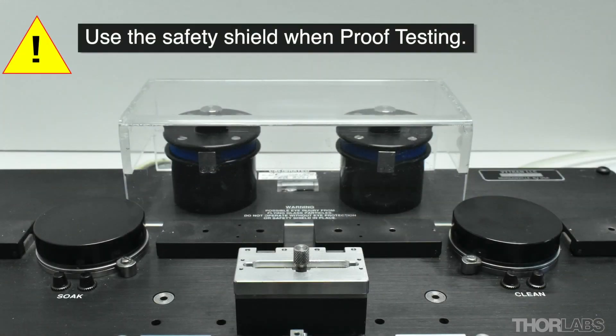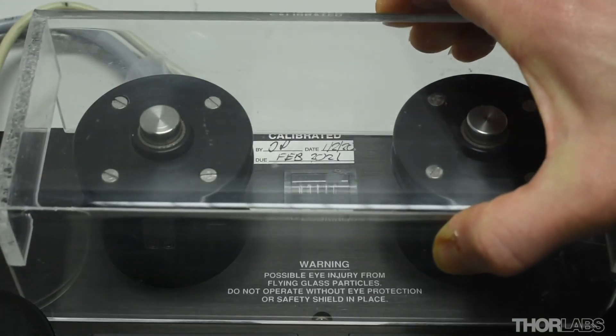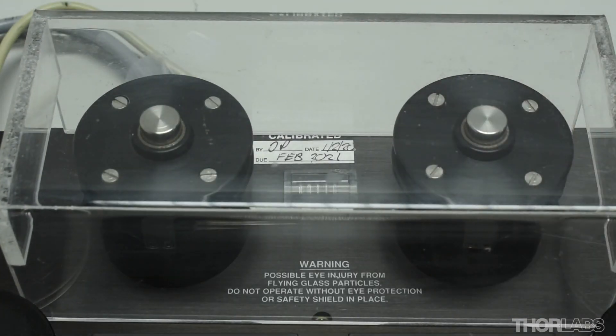The unit is provided with a clear plastic proof test shield, which should be used to contain the glass fragments should the fibre break.